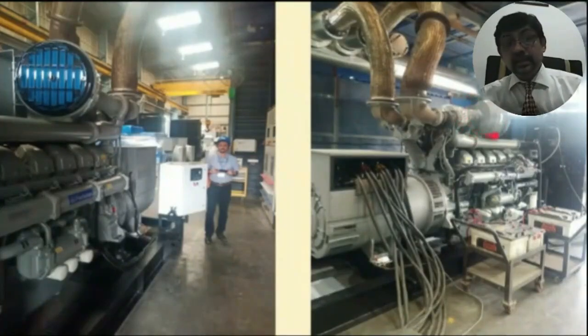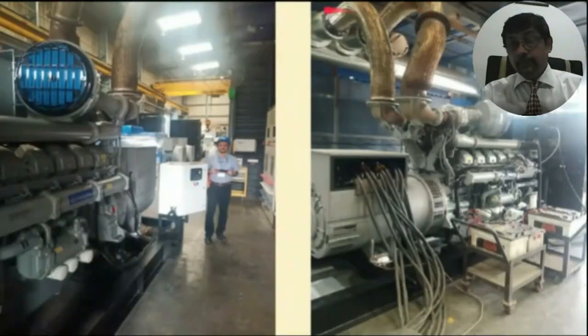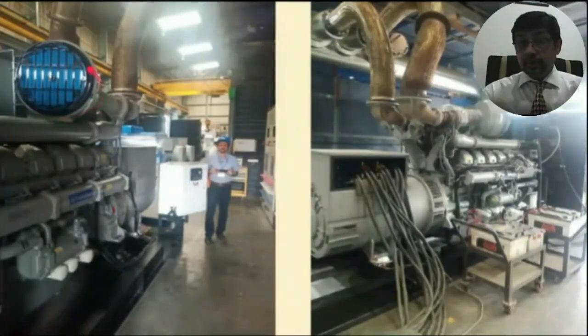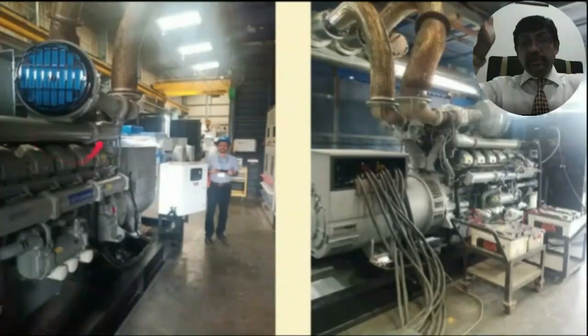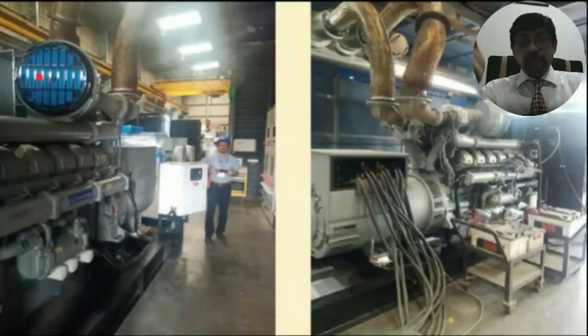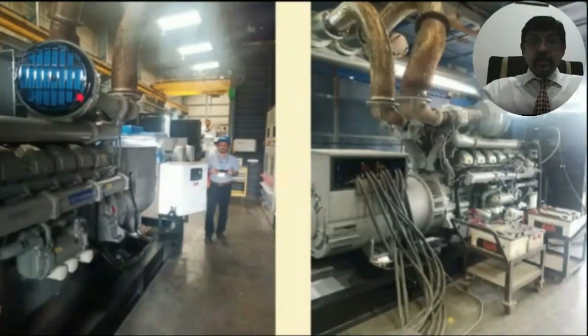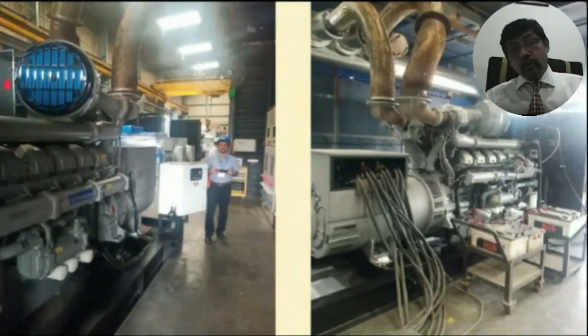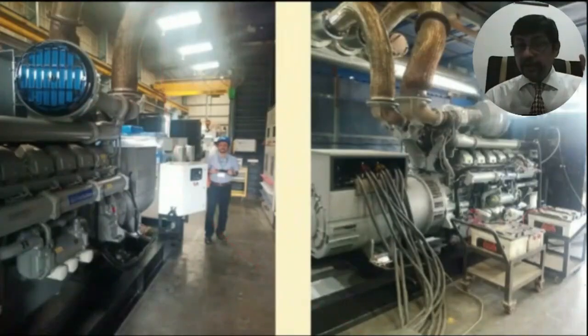This is basically the exhaust manifold, from where the exhaust flue gases come and then go via this exhaust pipe to the atmosphere. Of course, we have a silencer there, which can be seen on the right side of the picture. This silencer is basically to control the pressure with which the exhaust gases come out of the engine. The silencer is slightly wider in dimension. And from there, it goes up to the sky. So this is 30 meters high.